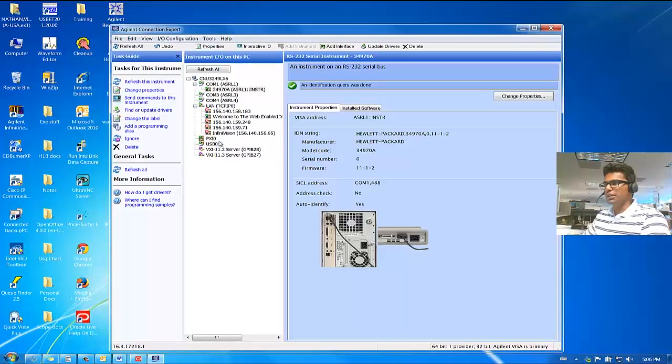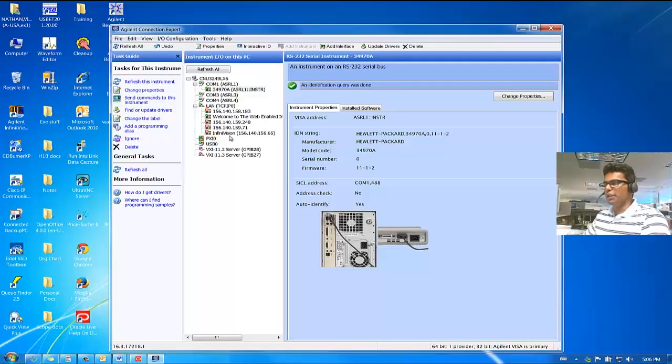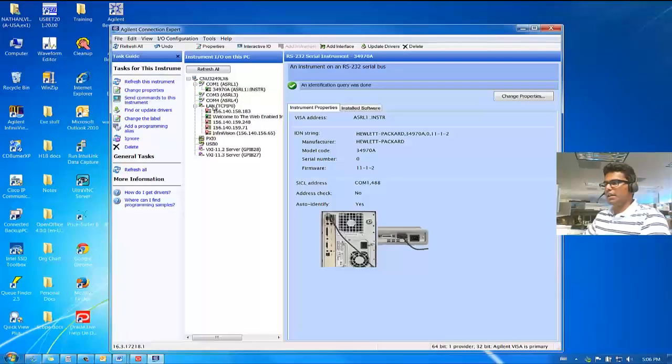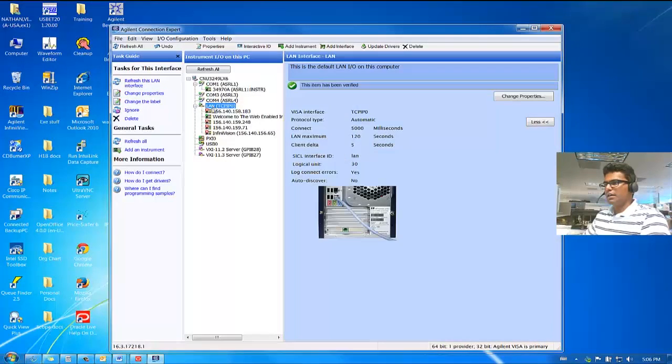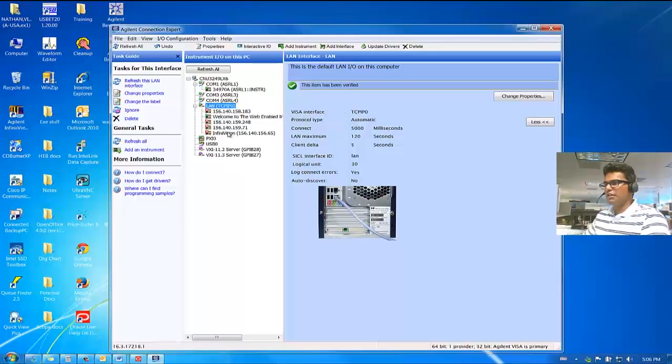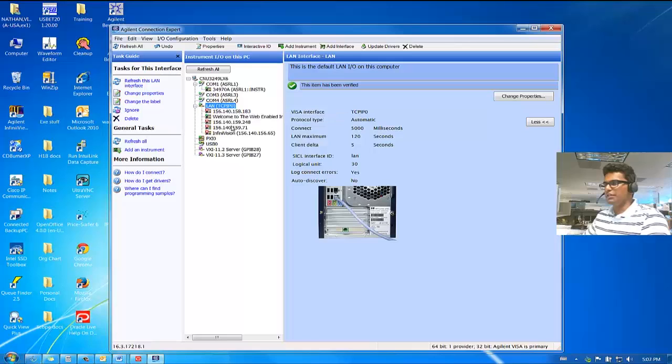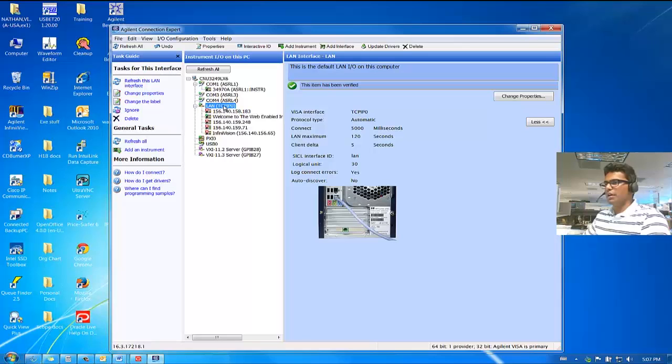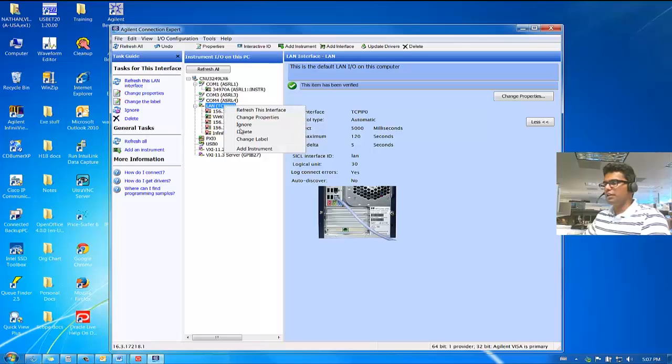Now, let's connect to the LAN interface of the 34970A. Click on LAN Connection. As you can see, I have a few other IP addresses. This is because I am connected to other instruments. But click on LAN, right-click on it and click on Add Instrument.